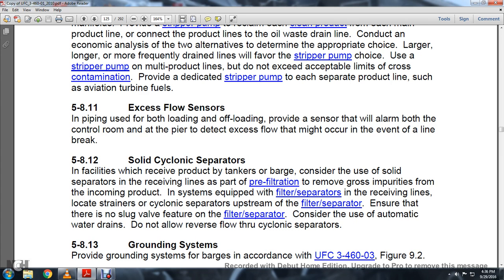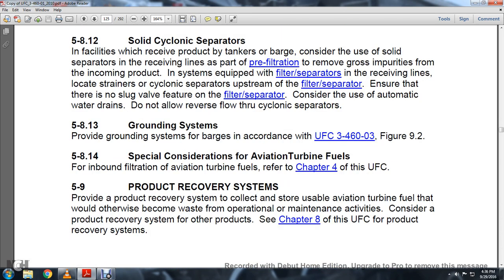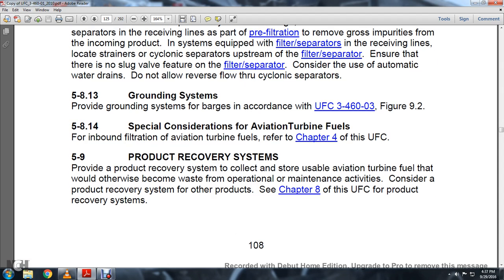Section 5.8.12 Solid Cyclone Separators: For facilities receiving product from tankers or barges, consider the use of solid cyclone separators on receiving lines as part of pre-filtration to remove gross impurities from incoming product. The system should be equipped with filter separators for receiving lines, with local strainers and cyclone separators upstream of the filter separator. Ensure there are no slug valve feature on the filter/separator, and consider the use of automatic water drains. Section 5.8.13 Grounding System: Provide a grounding system for barge income using UFC 3-460-03, Figure 9.2. Section 5.8.14 Special Considerations: For aviation turbine fuels and inbound filtration, refer to Chapter 4 of the UFC.